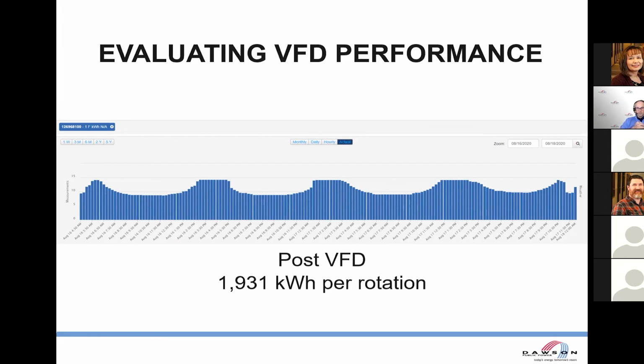Very commonly with VFD installation on a corner arm system, we've actually measured in the ballpark of 25% savings on energy use. That isn't going to improve your demand charges, but it will provide considerable savings on energy usage through the season -- especially this last season, it would have been nice to have those savings given how tough, hot, and dry it was.